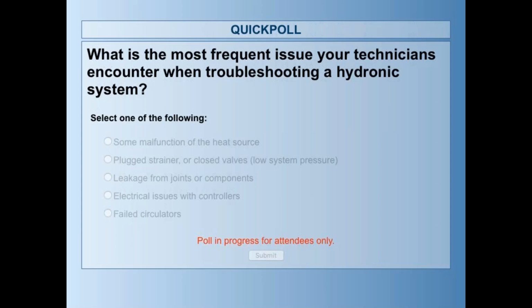One of the questions going back to, and we've had a couple come in the chat too while we're waiting for results. You wrote an article at one point about can you just turn up the pump speed to double the amount of BTUs in a zone? And you had an analogy with horsepower and cars and maximum speed. Could you give us kind of the 30-second version of that?